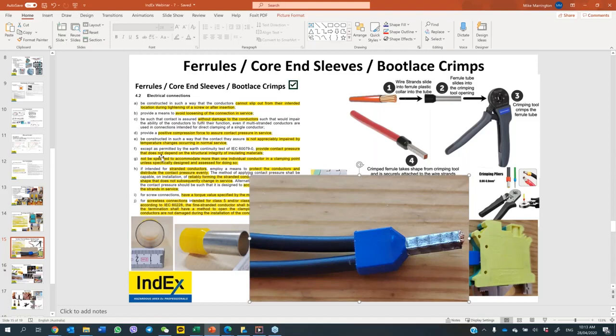Is it accepted to use insulated end caps for unused cables which are selected with suitable voltages? So I think what you're asking about is inside of an Ex e fluorescent lighting fitting. Sometimes you do have a clear kind of end cap that comes from the manufacturer. That's okay, that's part of the design. It's been tested and certified. No crimping of solid cores unless soldered and the crimp is designed for soldering. That's one comment from somebody, but basically, yeah, solids, 99% of the time, no, you don't crimp them.